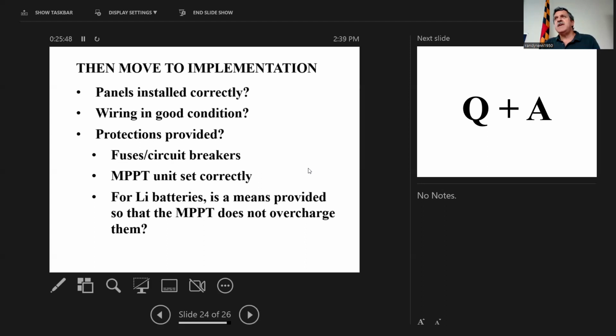There's an active means with a BMS that has some kind of relay output we can use to turn the MPPT off. Or, if we know the battery's maximum voltage and don't have a relay - if it's an internal BMS battery with no way to get that information out telling us it doesn't want to be charged anymore - we can know where that voltage limit is and force the MPPT to never go above it.